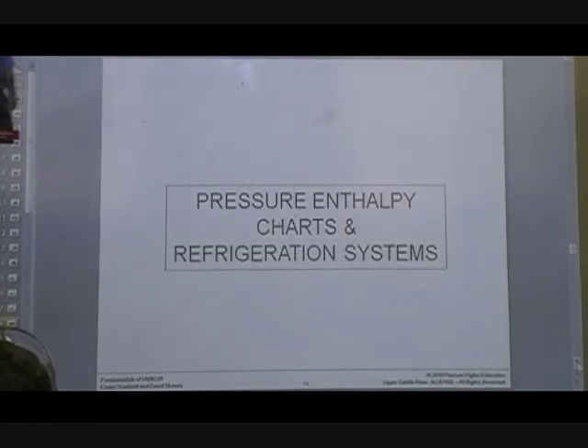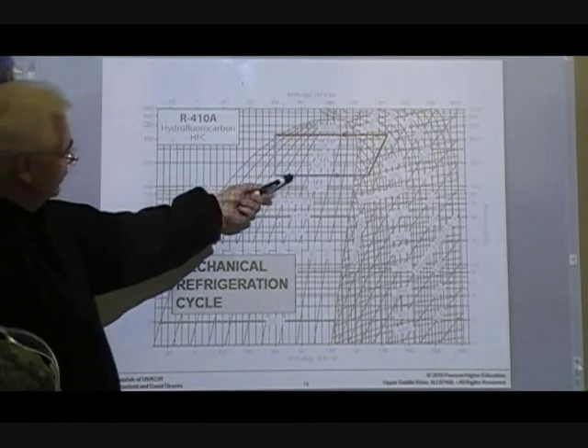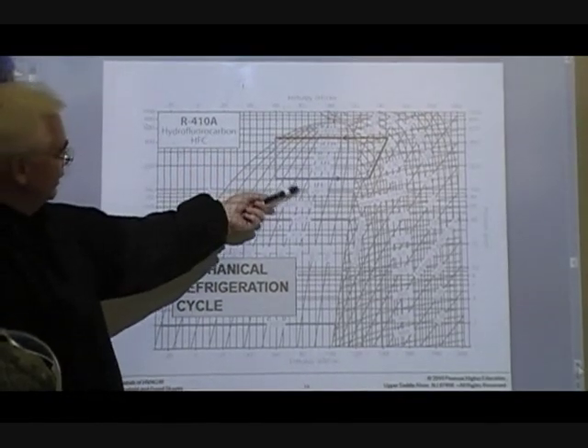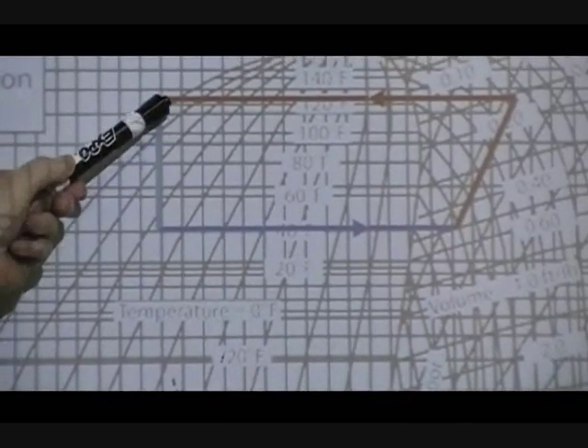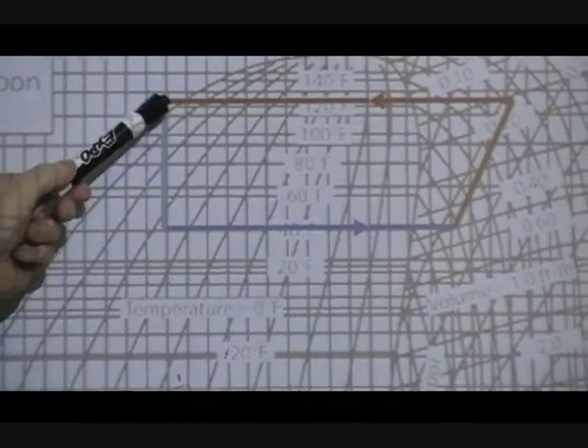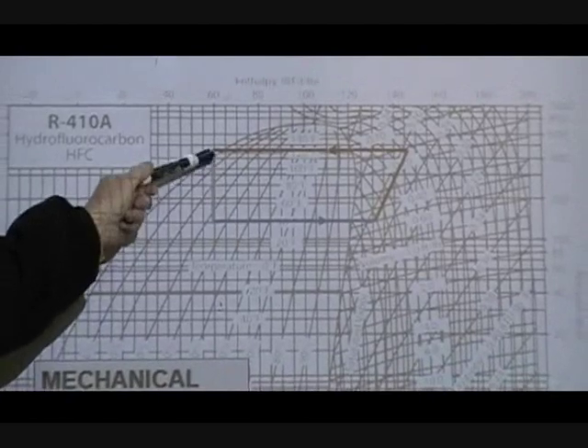We're going to cover pressure enthalpy charts and refrigeration systems. Now, this is where they have actually done some measurements for you. You look at your line, it's on 40 degrees, R-410A. This is an air conditioning system. You've got a 40 degree evaporator. And this is the point where the refrigerant enters the metering device. Notice that this is your 100% saturated liquid curve. And right in here is where this curve, where the liquid goes through the liquid line and enters your metering device.